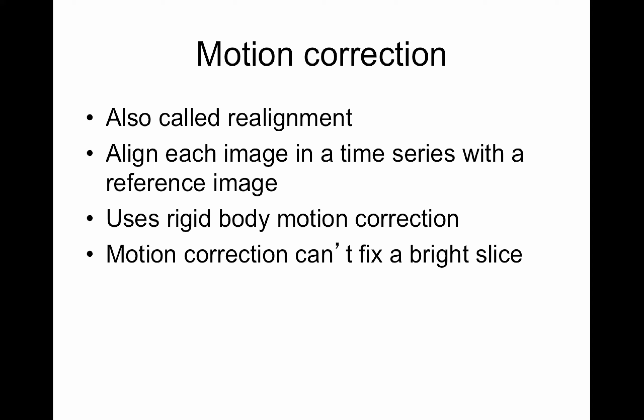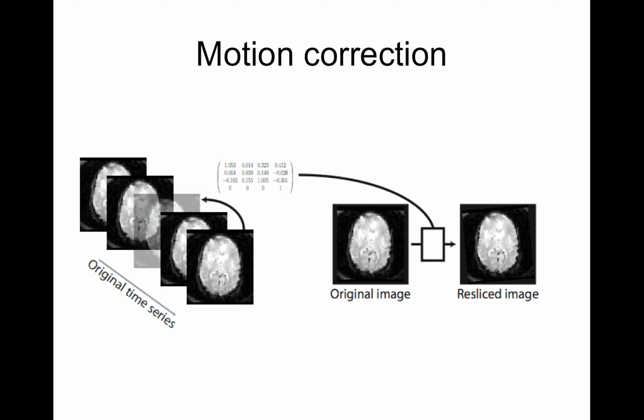Motion correction uses a rigid body correction, which means a six-parameter affine image transformation — only rotations and translations in X, Y, and Z are possible. This type of motion correction obviously can't fix something like a bright slice in the data. Usually when you have motion artifact with interleaved acquisition you'll get a bright slice, and this won't fix that. It also won't fix a corrupt TR where the whole image is really bright.